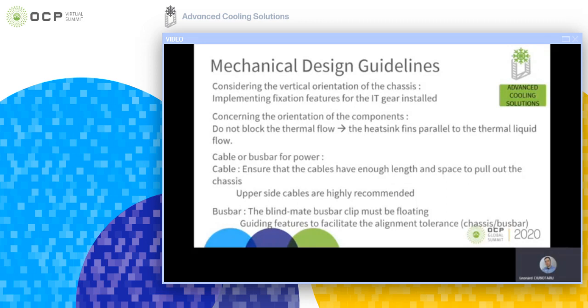Components positioning. The components should be positioned in such a way as not to hinder or block the thermal flow, or otherwise said, the movement of the immersion liquid. The positioning should allow the most surface contact in the direction of the liquid movement. For example, the heatsink fins should be parallel with the thermal liquid flow. Special attention should be given to plug-in components like PCI connectors, since the servers are installed in a vertical position. Could be that some type of fixture needs to be implemented to keep the components from disconnecting.